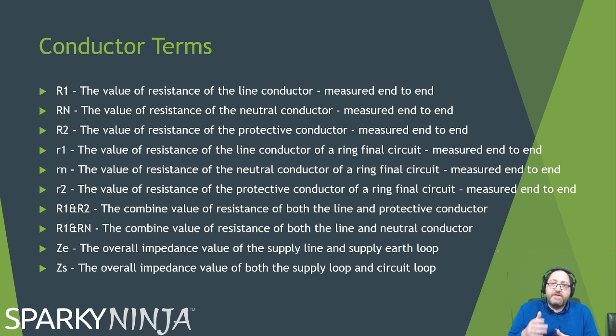Okay, so the ZE is the external earth fault loop impedance. So this is the resistance pathway that is supplying your installation. So take away your system, you won't have any of that connected. You'll take the earth out to remove the parallel, and you'll go from line to earth, and you'll get a measurement of that supply loop. If it's good, you'll use it. If it's not good, you'll keep your system de-energized and you'll wave to the supplier to fix it. And they'll probably tell you to put your spike in and make it a TT.